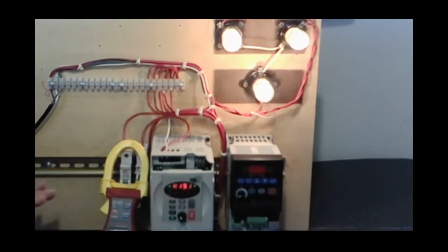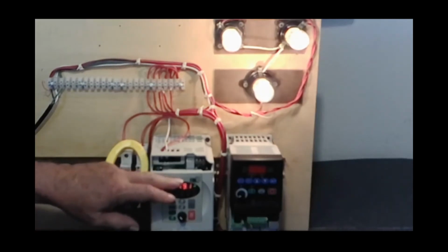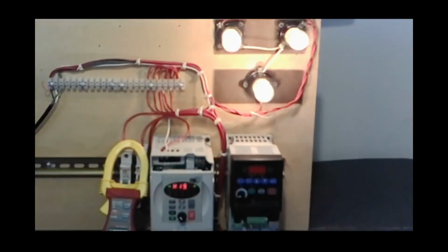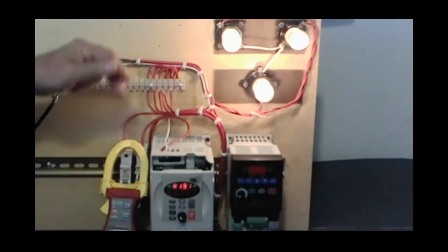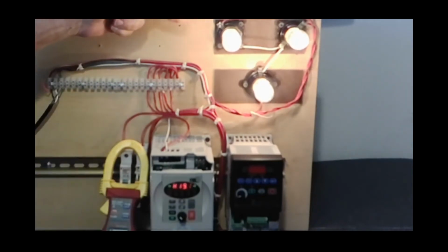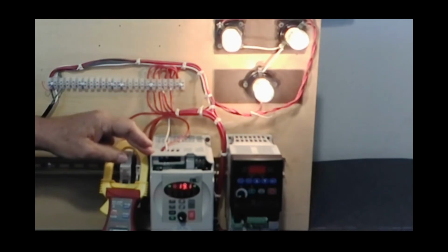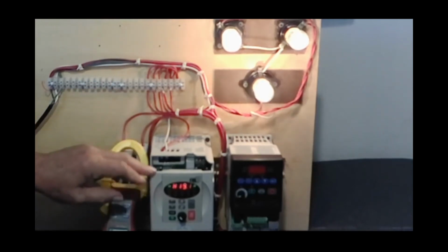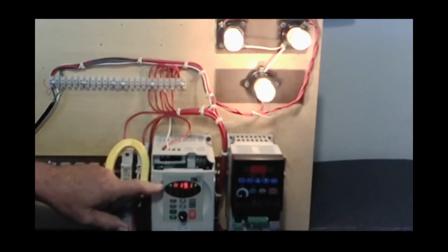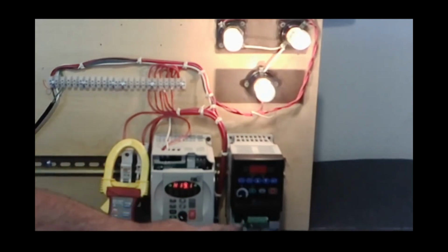So troubleshooting doesn't have to be rocket science. We do have to know which direction to go. If there's no error codes on the screen and we're not getting the proper voltages, we got a problem internally. If the drive just will not start or will not run correctly, it's going to be in a programming issue, or it's going to be in the inputs coming from another source. Very easily, you could have inputs from another source.